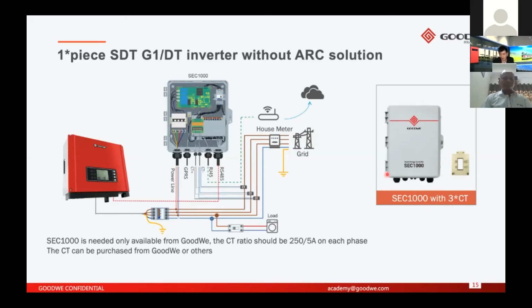But if you buy the CT in your local market, you need to remember that the secondary ratio of the CT should be 5. Like here it's 250 divided by 5. And if your load consumption in your house or in a factory is very high, you can buy a CT ratio like 500 divided by 5. Just remember the secondary ratio should be 5.